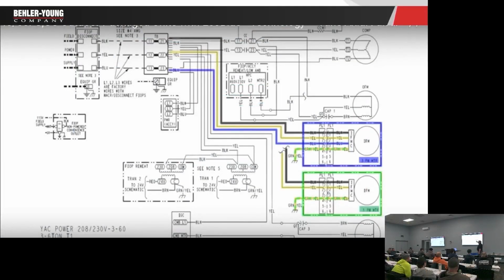Some of them are 3-phase, so I'd have a third wire. If I look at this wiring diagram right here, there's that terminal strip. You can see on a 3-phase, L1 black, L2 yellow, L3 blue. All three go to the motor, and you can see there's nothing breaking it. If the disconnect is on, that motor's got power. Again, if I get a power surge, that motor's taking it. Single phase like this one, it's just yellow and black, because it's a single phase.